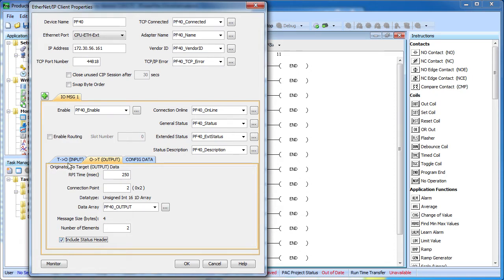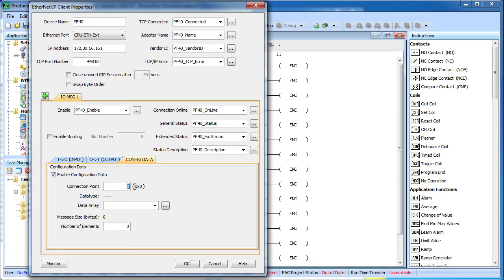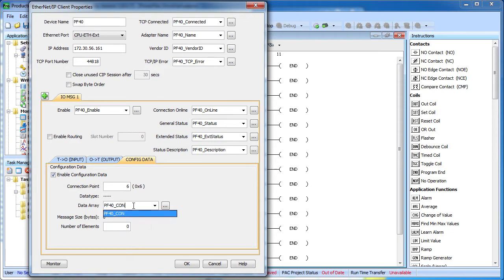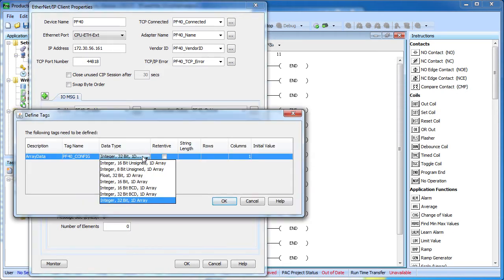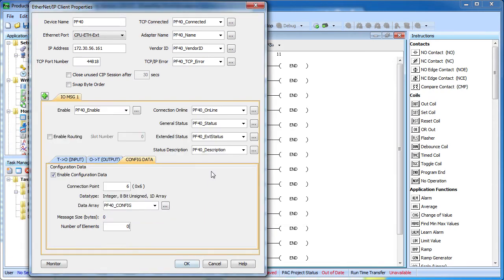We've done the input data, the output data, now we set up the configuration data. The configuration field is required for this drive, but with a zero data length. This drive uses 6 as the connection point, or assembly instance, and we do need to create a dummy array even though we're not going to use it. And I'll just set aside a little 8 bit unsigned integer 1 element.